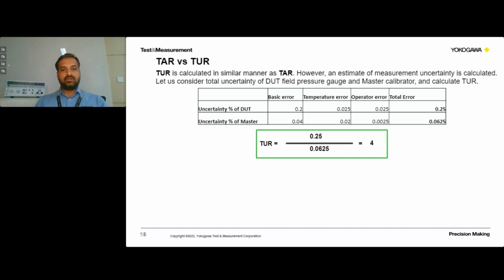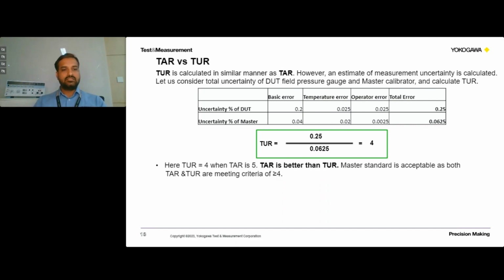And here you can see, with all these factors considered, 0.25 percentage is the uncertainty of the DUT, and 0.0625 is the uncertainty of the master. And we are checking the ratio here, and the ratio we are getting is just hitting the value 4. So it is equivalent to 4. So when test uncertainty ratio is 4, we are hitting the TAR value of 5. That means TAR is better than TUR. So master standard is acceptable as both TUR and TAR are meeting the criteria of greater than or equal to 4. That means our TAR cannot be lesser than our TUR. So that's what we want to convey from these two slides. So we cannot have a lower TAR than TUR.